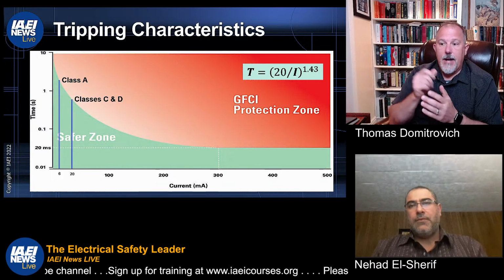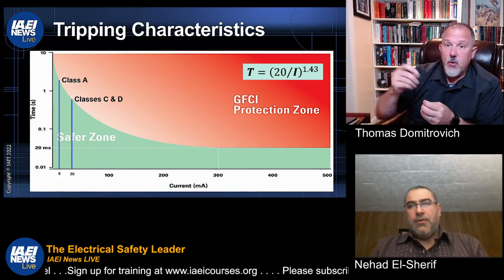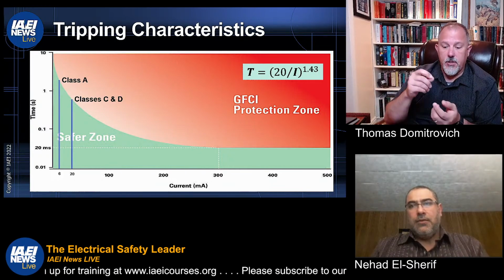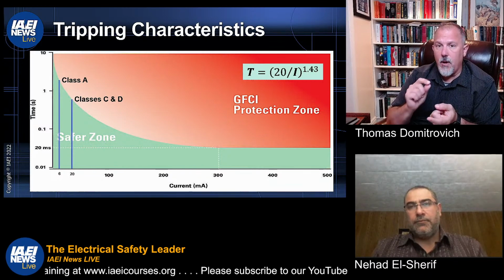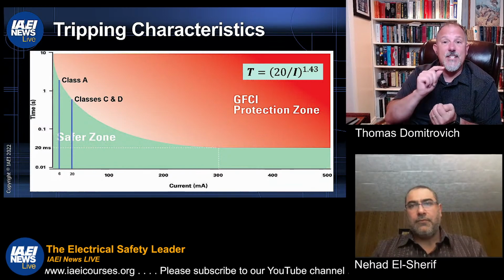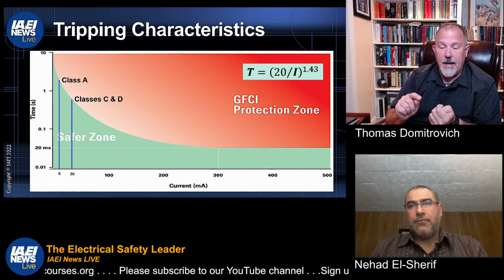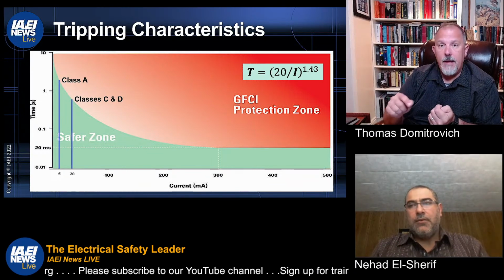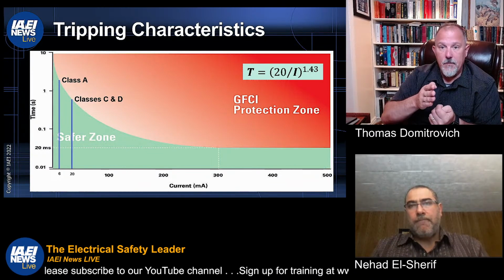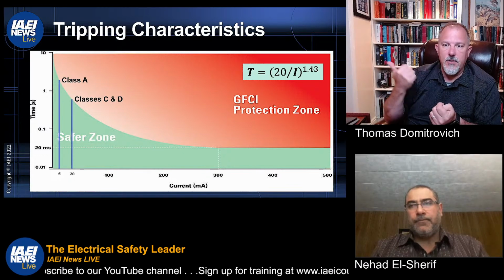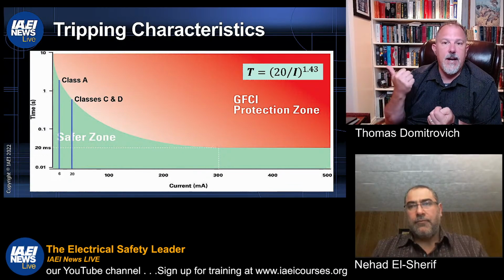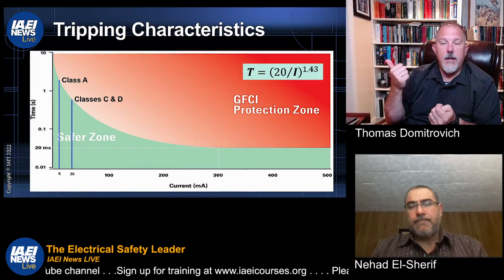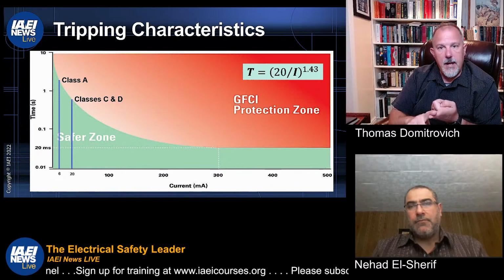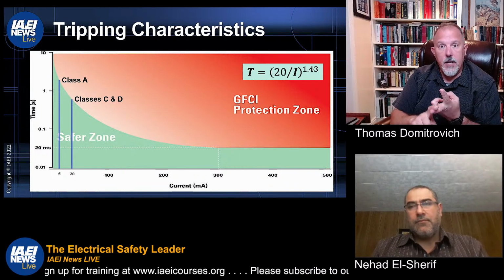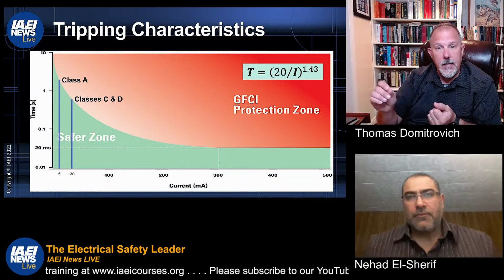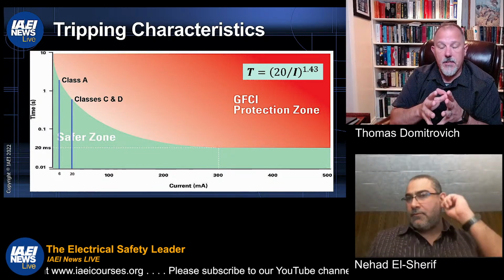But now there is ground fault protection of equipment in marinas. Article 555 has requirements for 30 milliamps, but that's GFPE. That's not GFCI. That's ground fault protection of equipment at 30 milliamp pickup. And the clearing times don't use the same equations that you have for GFCI. All we're worried about in using the 30 milliamp or the 100 milliamp ground fault protection of equipment in marinas is to detect a problem in the circuit.